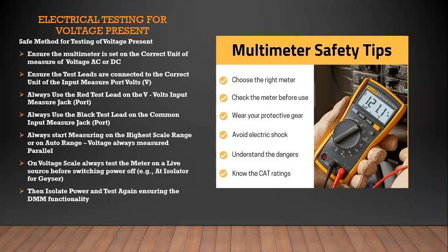Also, I explained to you how to test your meter, because a lot of people take the meter out of the toolbox, go switch it on, test, and after they've switched the power off, and that's not correct. You first test your meter with power on, and then switch the power off and test again. Then you've tested your electrical test instrument that it's actually functioning correctly before you isolate. Then you can trust the instrument, because that instrument is your lifeline. You're trusting the instrument that it tells you there's no voltage present, and you touch those bare wires to loosen the wires on the element, for example, to change the element on the thermostat. So testing the meter is of utmost importance, and very few people actually do it correctly.